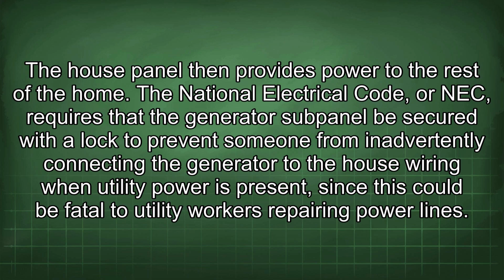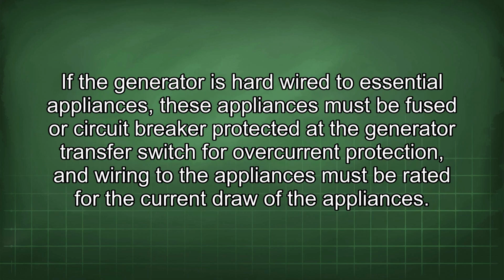The National Electrical Code, or NEC, requires that the generator subpanel be secured with a lock to prevent someone from inadvertently connecting the generator to the house wiring when utility power is present, since this could be fatal to utility workers repairing power lines. If the generator is hardwired to essential appliances, these appliances must be fused or circuit breaker protected at the generator transfer switch for overcurrent protection, and wiring to the appliances must be rated for the current draw of the appliances.